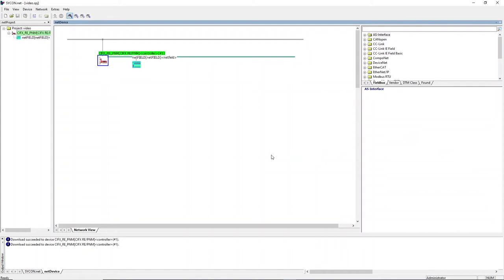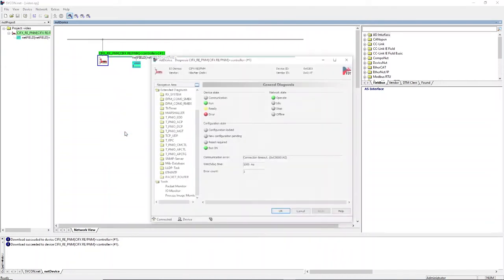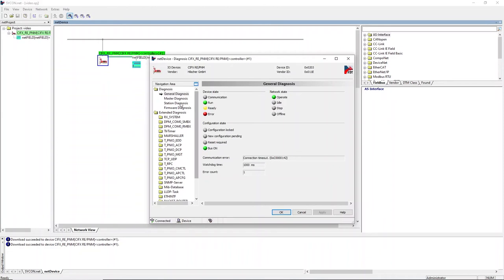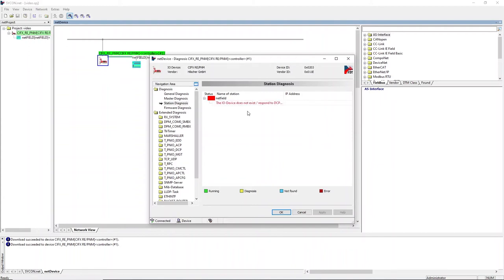Open the diagnosis to see the current state of communication. As we can see, there is currently no communication established. The station diagnosis indicates that there has been no response to the DCP IDENT request of the IO controller. Since the name of station for the NetField IO device has not been set yet, this is an expected behavior.